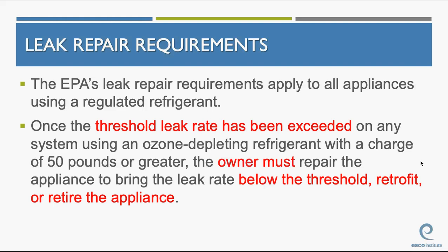The EPA leak repair requirements apply to all appliances using a regulated refrigerant. Once the threshold leak rate has been exceeded on any system using an ozone-depleting refrigerant with a charge of 50 pounds or greater, the owner must repair the appliance to bring the leak rate below the threshold, and they have to retrofit or retire the appliance.